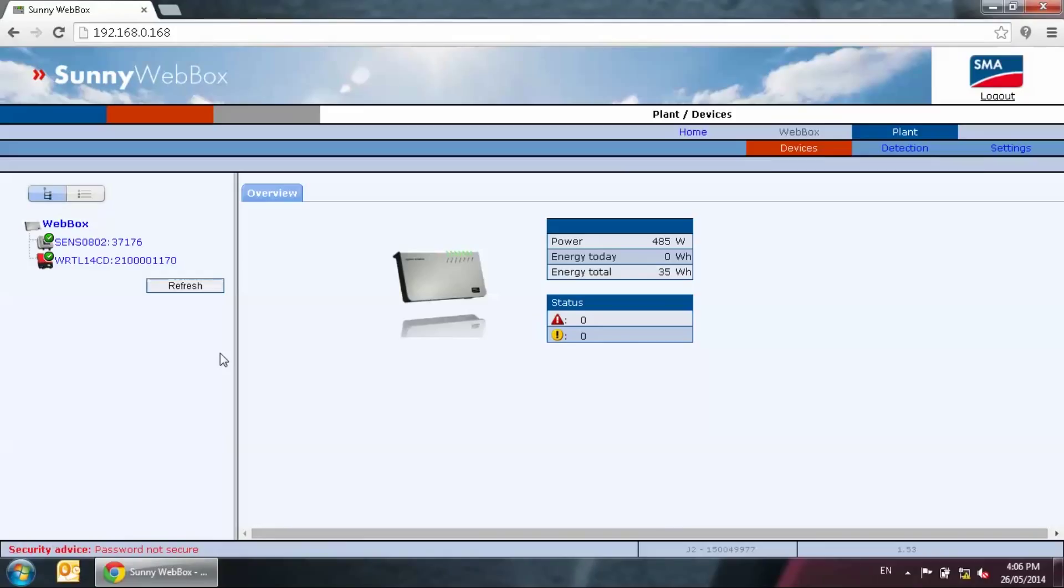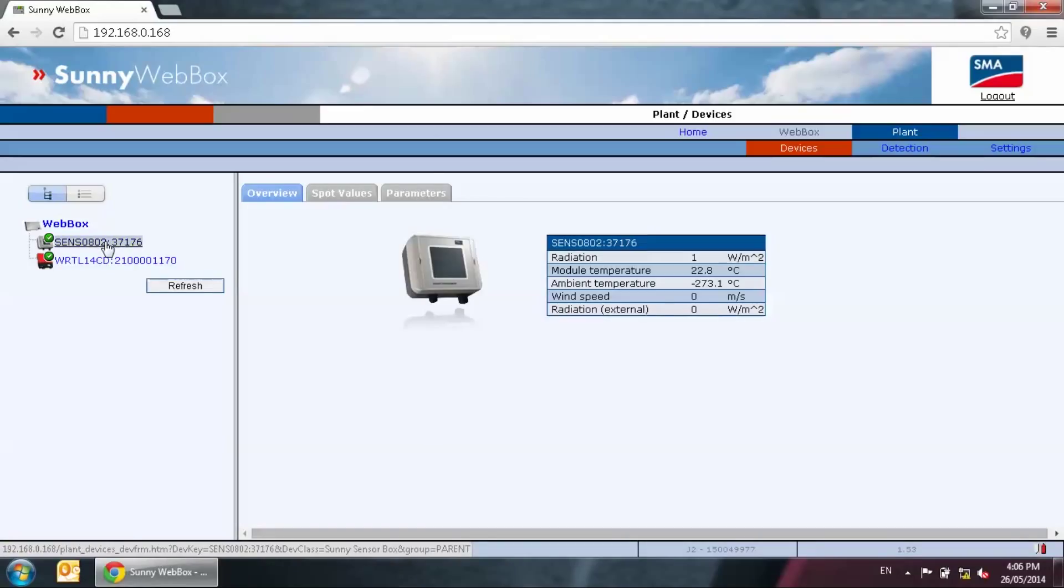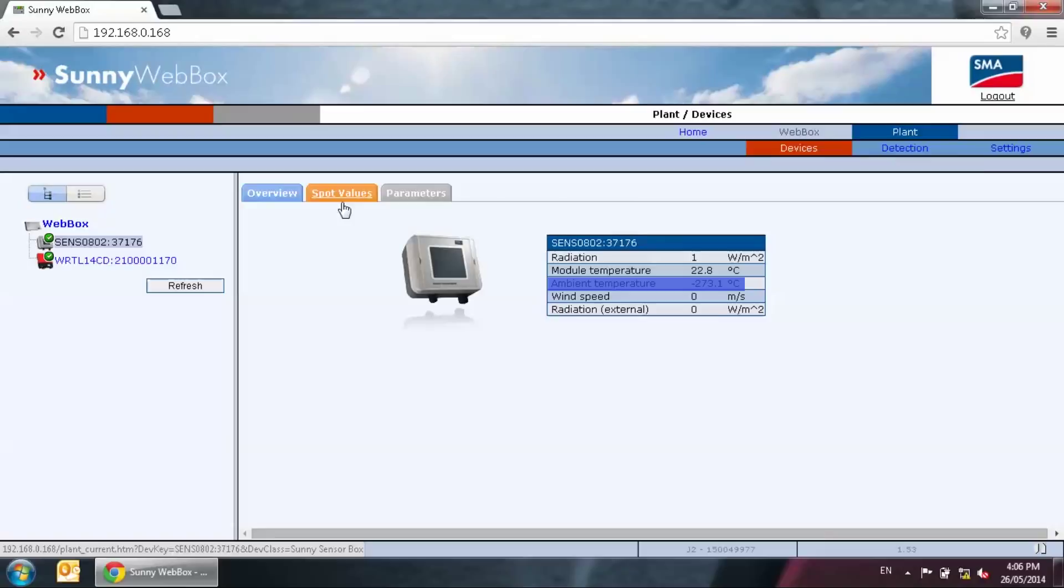Devices that are in normal operation will show a green tick. Devices that are not well detected will show a grey dotted icon. If that's the case, you will need to perform a full detection once again. If you have a sensor box connected, please check the spot value by selecting the sense device and click spot value. Check the ambient temperature, the wind speed and the module temperature. See if they are having a correct value. Pay attention to the ambient temperature. If it's showing negative 273 degrees, it means that the wiring is incorrect.